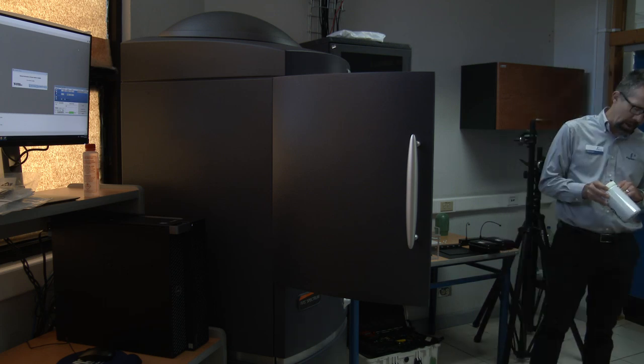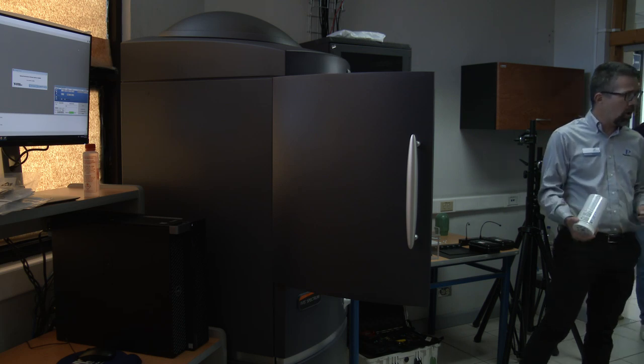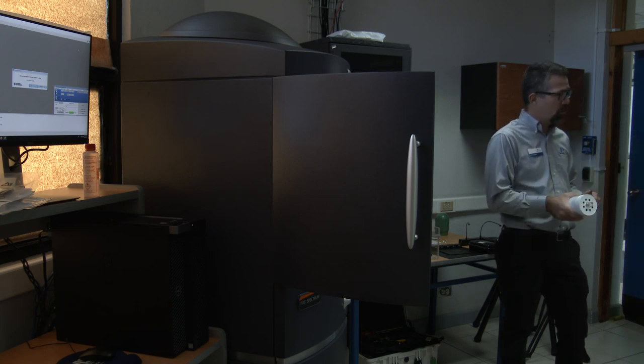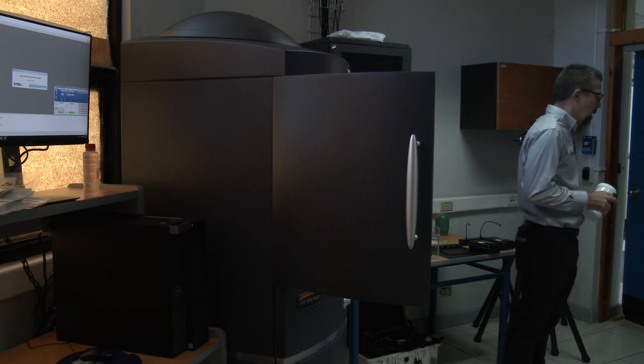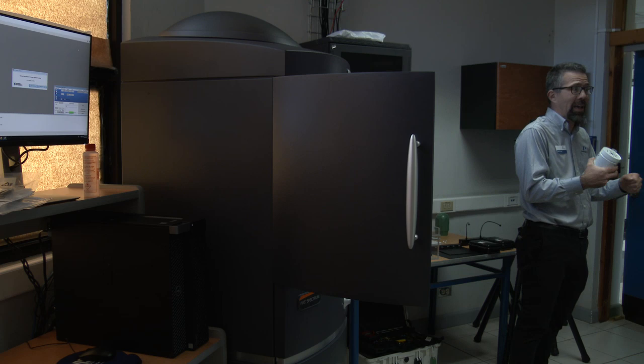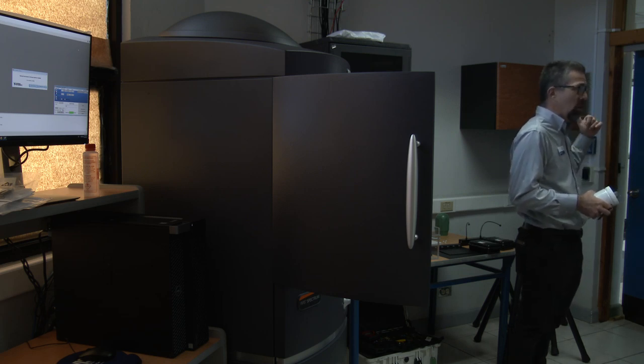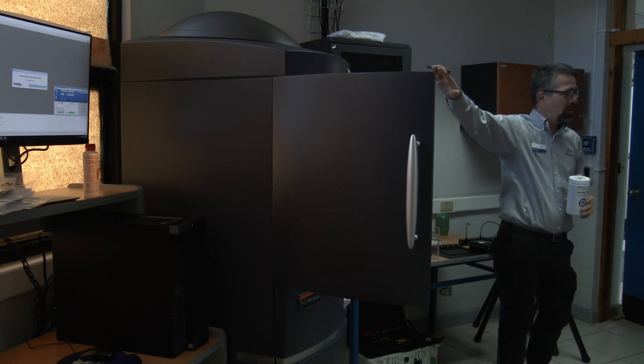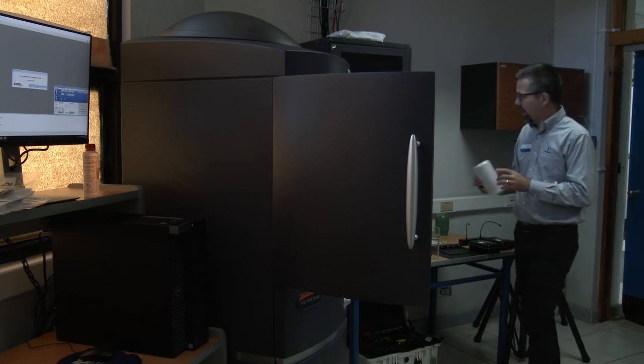It has a weight, and when the weight increases by 100 grams, we're going to dump the charcoal out. You take the lid off, you dump the charcoal out, you refill it with activated carbon, and you do it. When I dump this thing out, I put it into a bag, then I close the bag up, and I put it outside by the dumpster, or I'll put it inside of a hood, and make sure the hood vents to the outside, right? There's some precautions that you have to take with isoflurane.